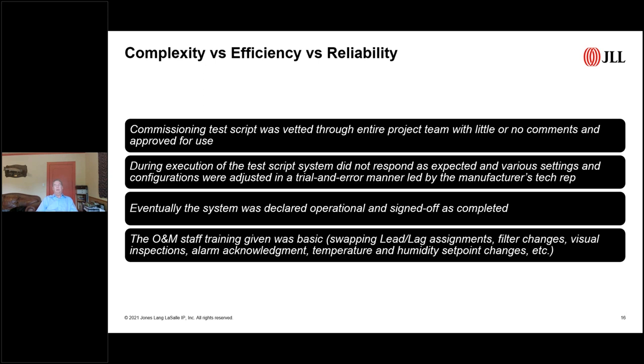The commissioning test script had been vetted through the entire team. Everybody said it was good, no comments back. But when we were executing the test script, it became apparent it wasn't working the way we thought, and the manufacturer's technical rep started troubleshooting in a trial and error manner, just trying things to see what would work. Eventually the system did what it was supposed to do.